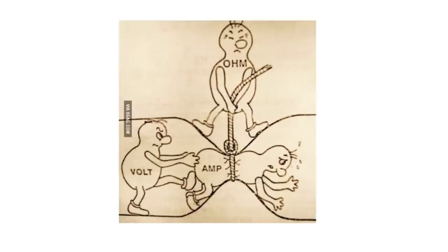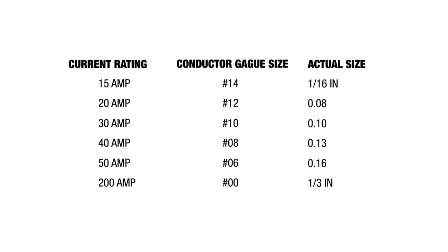Now we can look at a chart, and amps, remember, is like the pipe size. The chart will say that a 15 amp circuit uses a number 14 gauge wire, and the actual size is about a 16th of an inch. And a 20 amp circuit requires a number 12 gauge wire. Remember, in metal, as we go lower in number, in gauge, we get thicker. And the actual size is a little bit bigger, 0.08 inches.